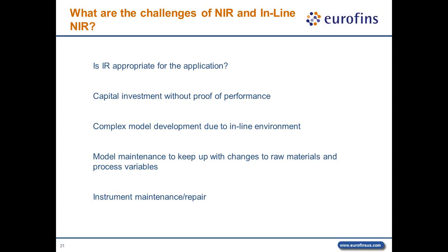Outside of having the hardware and instrumentation you need, model development is the most technically challenging aspect and becomes increasingly more complex when you take the point of analysis inline. Model development for benchtop systems allows for a stable, repetitive environment with a controlled sample. Your variables are reasonably constant, and you have more favorable conditions for capturing your spectrum. Inline model development introduces additional areas of complexity because you must account for changing conditions and moving material. Temperature variation throughout a reaction, pressure fluctuations, flow rate, and turbulence must all be treated for in the models. In addition, anytime there is a significant change to the raw materials or process variables, the models must be adjusted to treat for these new factors, which ultimately have an effect on the spectra.